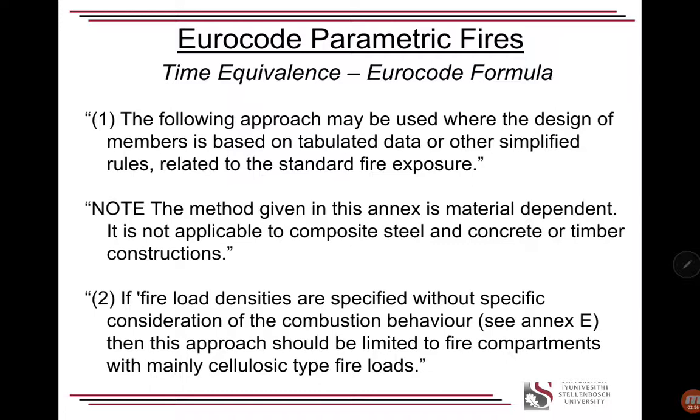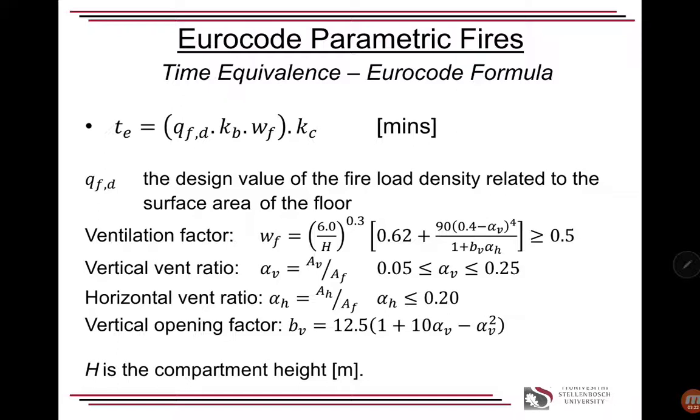So this is a quote directly from the Eurocode annex: The following approach may be used when the design of the members are based on tabulated data or other simplified rules related to the standard fire exposure. Note the method given in this annex is material dependent. It is not applicable to composite steel and concrete or timber constructions. If fire load densities are specified without specific consideration of the combustion behavior, and there's some discussions in Annex E, then this approach should be limited to fire compartments with mainly cellulosic type fire load. So you shouldn't be using it for petrochemical fires.